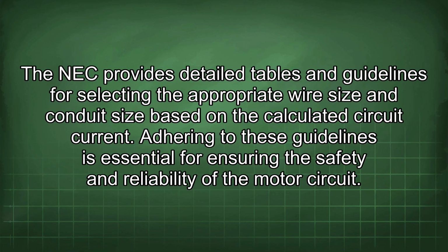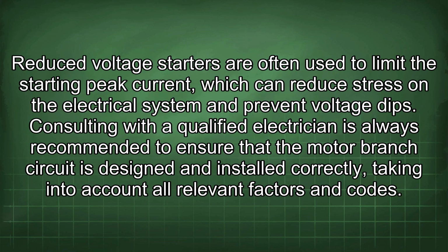The NEC provides detailed tables and guidelines for selecting the appropriate wire size and conduit size based on the calculated circuit current. Adhering to these guidelines is essential for ensuring the safety and reliability of the motor circuit. Reduced voltage starters are often used to limit the starting peak current, which can reduce stress on the electrical system and prevent voltage dips. Consulting with a qualified electrician is always recommended to ensure that the motor branch circuit is designed and installed correctly, taking into account all relevant factors and codes.